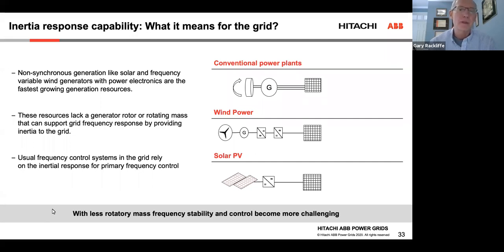Now, a battery operates similar to solar PV in so much as you have a converter, inverter as part of the power conversion system, which means it's bi-directional. Solar PV inverters are only one direction, but batteries are bi-directional. With a battery, you can actually inject real power. So in that regard, it can help support the grid during an event. And I'll talk a little bit more about the role of storage in a moment. But the key takeaway is that power electronic connected generation resources do not contribute to grid inertia, which makes the grid more susceptible to frequency decay whenever there's a disruption to the grid. So it becomes an operational challenge.